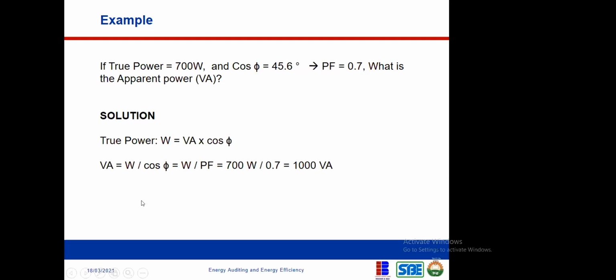So it means if I am buying a generator for an inductive load with a power rating of 700 watts, I should go for a generator rated 1000 VA or 1 kVA, am I right? Exactly. So if I'm going to the market to power my inductive equipment, motor or whatever has a coil, I'm not going to buy a generator of 700 watts, rather I'll go for an apparent-rated machine, a generator of 1 kVA.